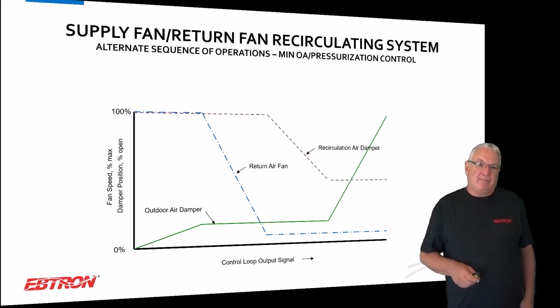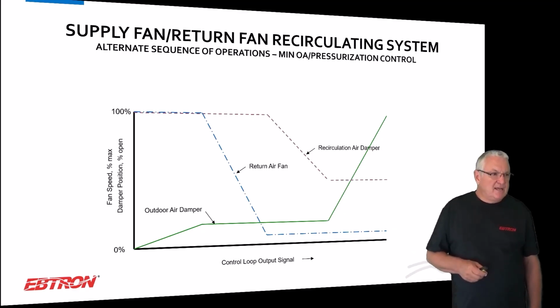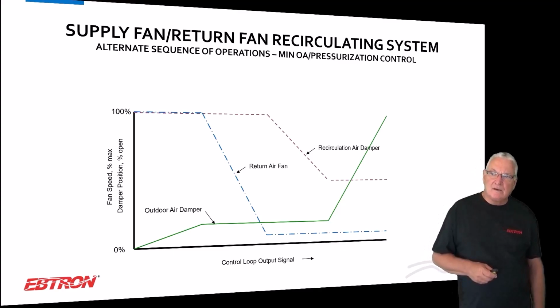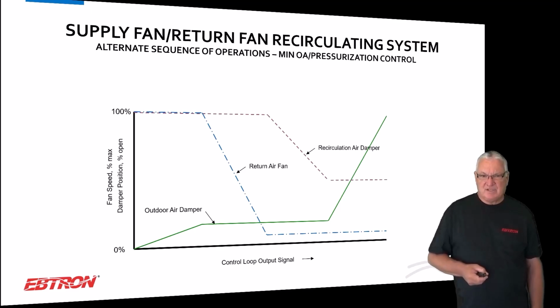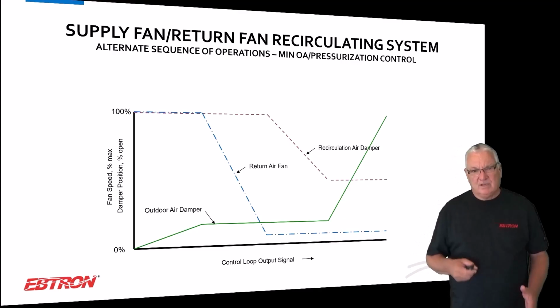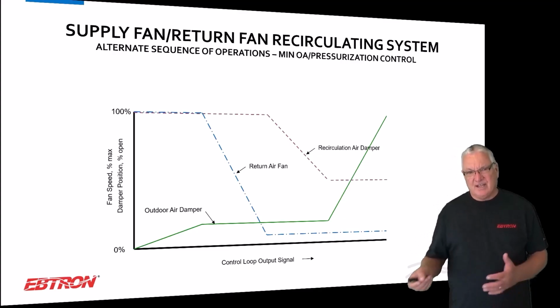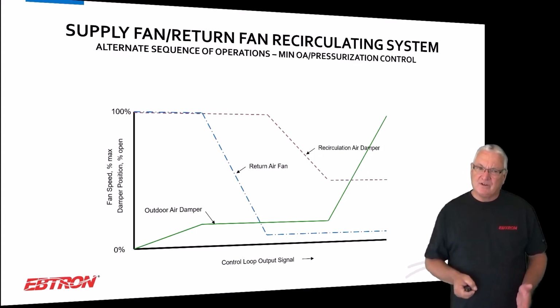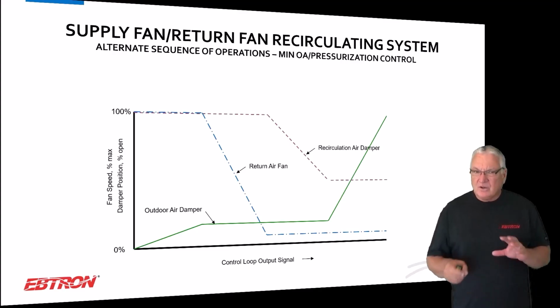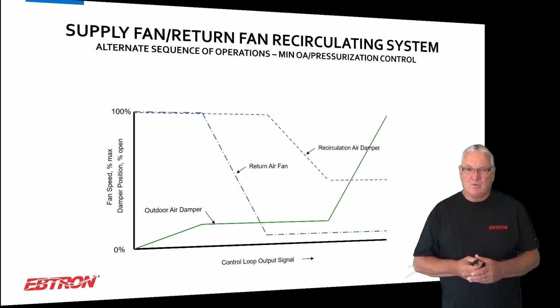Okay, there is an alternate. Sometimes we get into cases, not so much in healthcare, but more in offices, large older cities, with oversized intake dampers that you can't really measure well, because they're so large. That means you can't control them either. The measurement's going to be difficult. So there are all kinds of criteria here that we're going to want to look at.